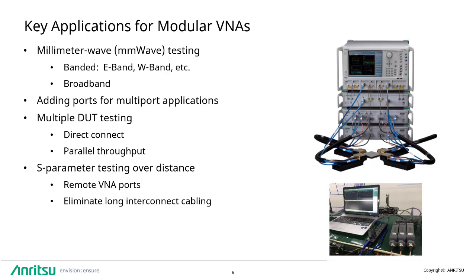Here are some examples where modular VNAs show significant advantages. Millimeter wave testing. Support for modular frequency extenders is key for this sector. Coax test port cables are no longer a viable solution to connect an integrated VNA to a device under test at these high frequencies.